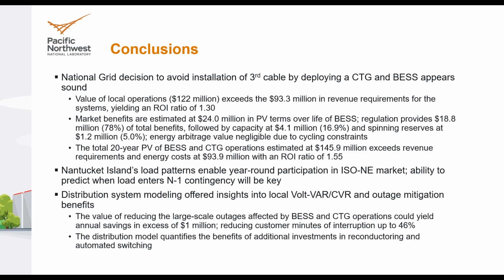Finally, we have this distribution system model that's allowed us to zero in on the volt-VAR, CVR, and outage mitigation benefits. We've demonstrated that if all the investments were made—the energy storage system and CTG—and operated optimally, you could avoid on the island up to 46% of the customer minutes of interruption. That's a significant resiliency benefit.